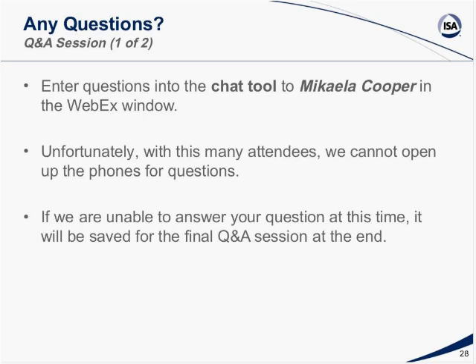Our next question is, NFPA 85 applies to boilers only. Section 1.1.3 states, this code does not cover process heaters used in chemical and petroleum manufacture in which steam generation is incidental to the operation of a processing system. What standard should be used for furnaces and burners that are not boilers? NFPA 86 is one, and also NFPA 87. Heaters are covered under 87.